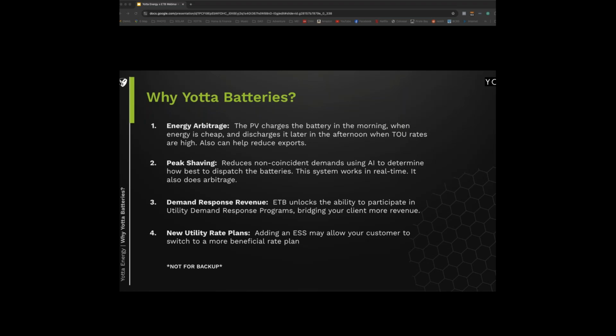Peak shaving is all done with Energy Toolbase's Acumen hardware, which controls the dispatching of the batteries, and it's done in real time. We'll monitor the building load, and if we determine the HVAC system kicked on, or maybe it's a medical building with X-ray machines turning on and off all day that draw a lot of kW from the grid, our system can view that and dispatch the batteries to offset those high demand charges.